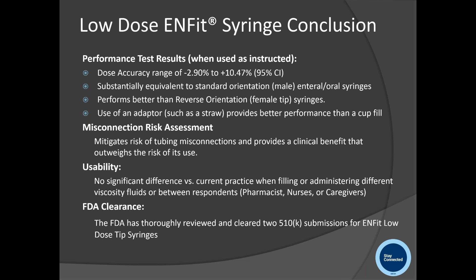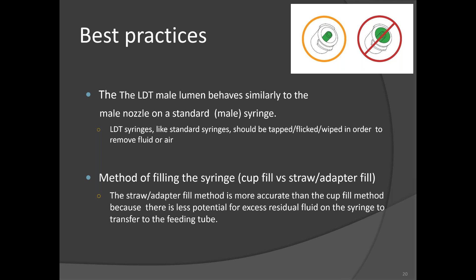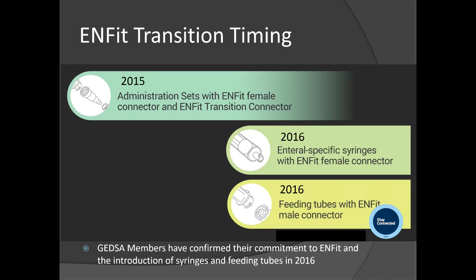From a best practices standpoint, we believe the low-dose tip male lumen behaves similarly to the male nozzle on a standard male syringe. One thing that we want to be clear about, though, is that when you are filling from a cup, there is a potential for medication filling up in the moat area of the syringe, and that's the green part over here. So we recommend, just as you would flick a syringe to remove the air bubbles, you're also flicking that syringe for a new purpose, and that is to remove any fluid from the moat. And that's a best practice to ensure delivery of an accurate dose. In terms of the transition timing, we are recommending the introduction of ENFit feeding tubes and syringes as soon as possible with adequate supply to meet your patient and healthcare needs.